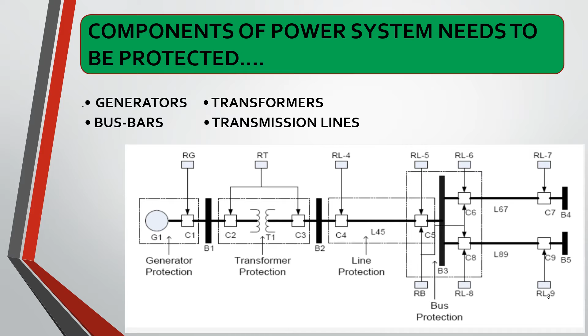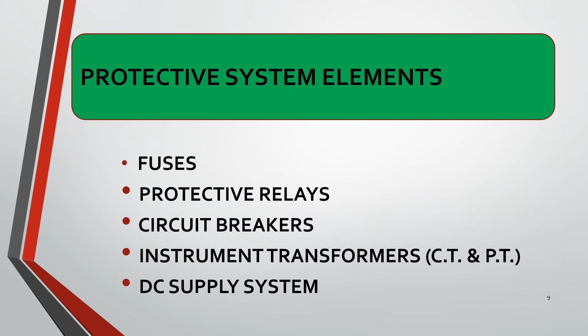Protective system elements. We are all well familiar with low voltage switches and rewirable fuses. A switch is used for opening and closing an electric circuit, and a fuse is used for overcurrent protection. Every electric circuit needs a switching device and a protective device. The switching and protecting devices have been developed in various forms. So fuses, protective relays, circuit breakers, instrument transformers like current transformer, potential transformer, all are the elements of protective system. And one more thing is given here, that is DC supply system. We need to provide excitation or DC supply for the operation of protective relays and circuit breakers.